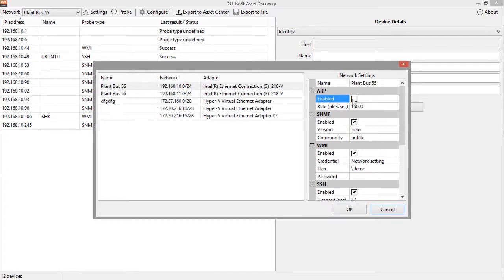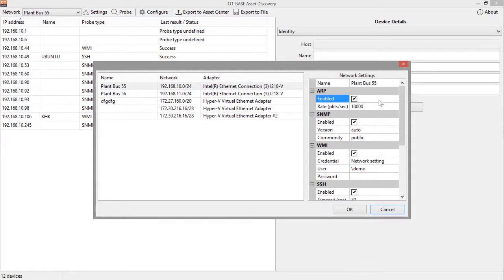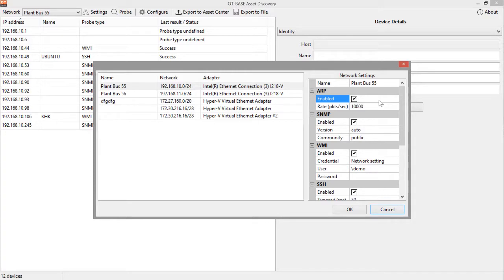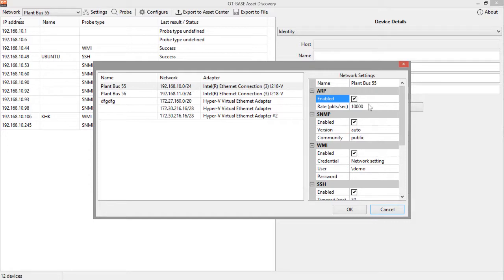First, you can check this box on or off to tell OT-BASE Asset Discovery if it shall send out ARP requests in order to identify devices in this network segment. If you deselect this box, your probing will be quite limited because OT-BASE Asset Discovery will not be able to identify any device on the network other than those devices that are already known. So, we strongly suggest to select this box.